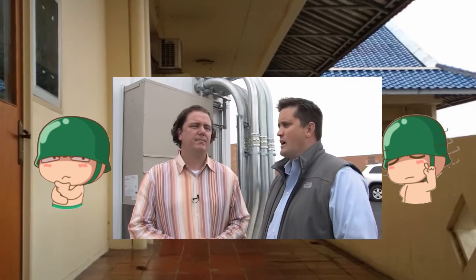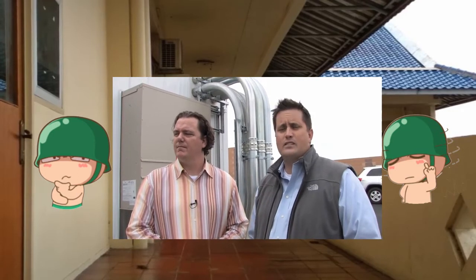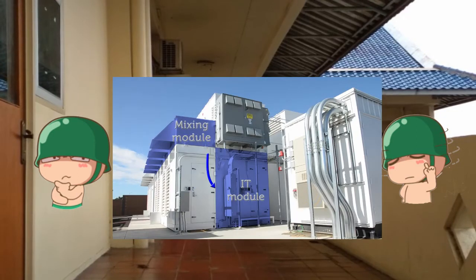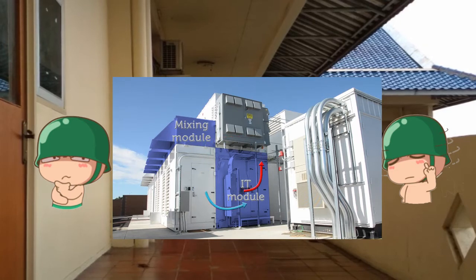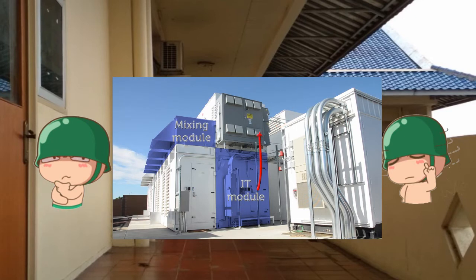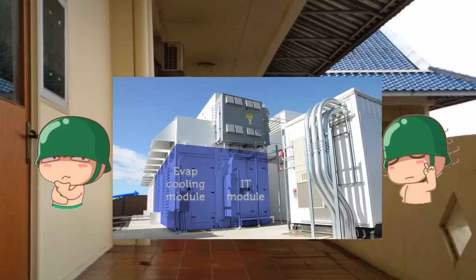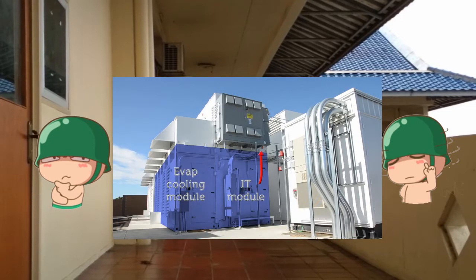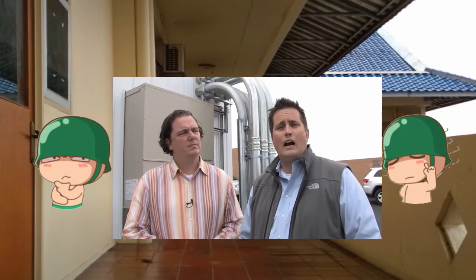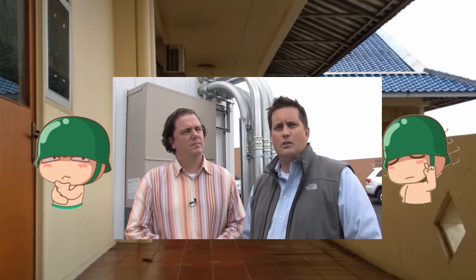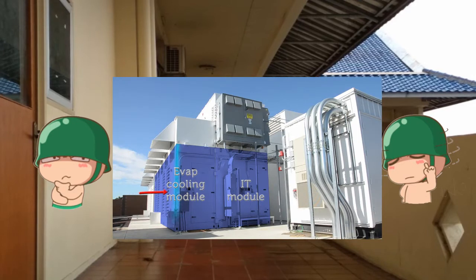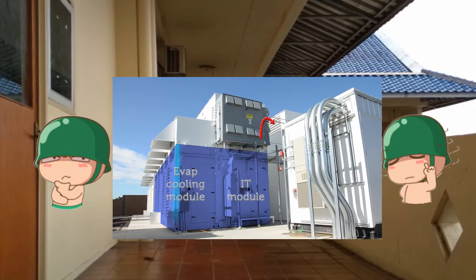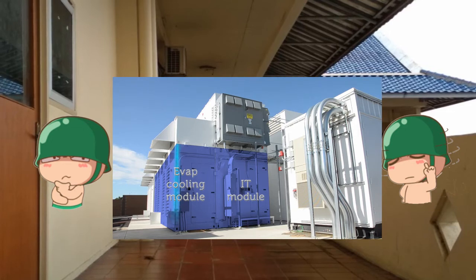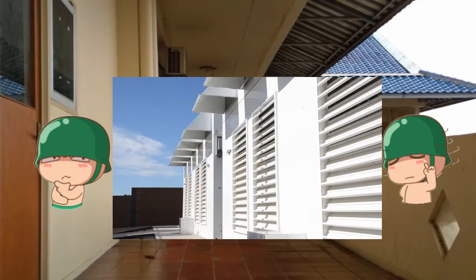This has three basic modes of operation. You're either operating in a mixing mode, where you're taking the return hot air from the IT and remixing it with outside air to get the ambient temperature at the inlet to the servers that we wanted. The second mode is the traditional outside air mode, where you're pulling in outside air that is filtered across the servers and does not require anything other than an air mover to facilitate the cooling. The third is when it becomes too hot. What this customer selected and what we've now deployed for them is direct evaporative cooling, using a type of swamp cooler technology to remove energy from the air and thereby reduce the inlet temperature from the outside to the servers.